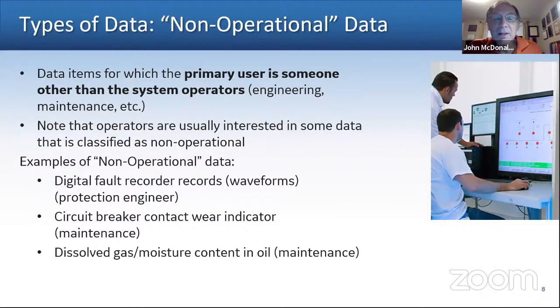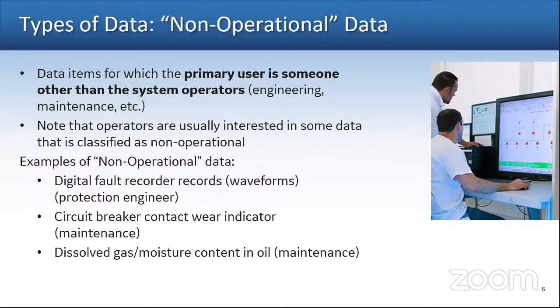By a data file, I mean it could be a digitized waveform from a microprocessor-based device, like an oscilloscope waveform that we've digitized. It could be a point, such as circuit breaker contact wear, which we'd send to maintenance. Or in a transformer, it could be how much gas is dissolved in the oil of the main tank—again, maintenance would be interested in that. So non-operational data is points or files.